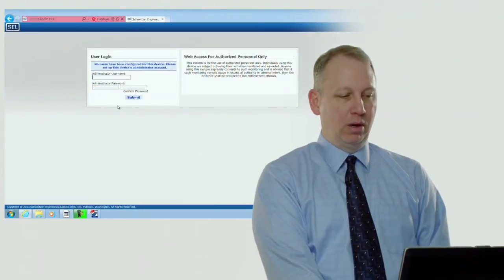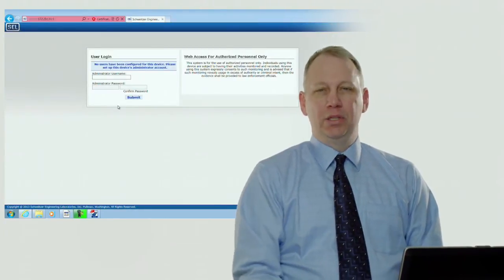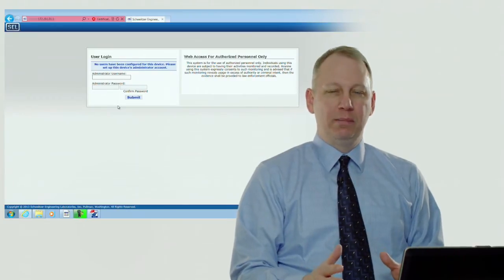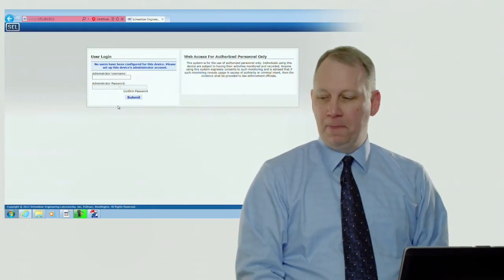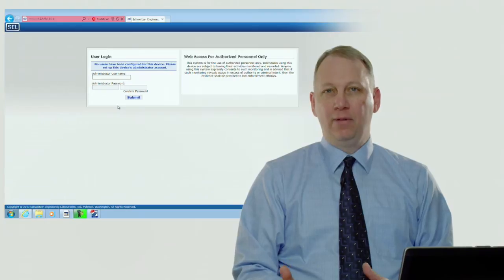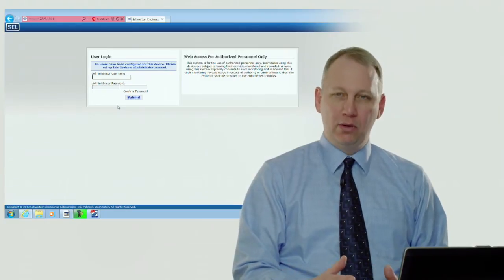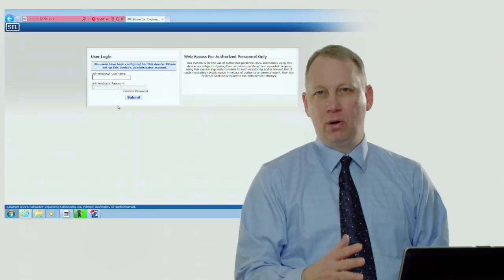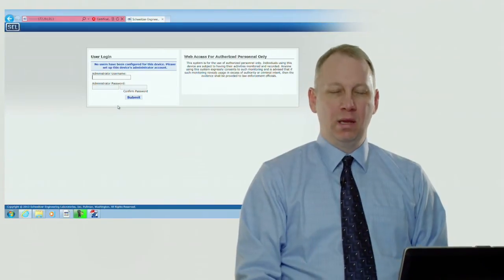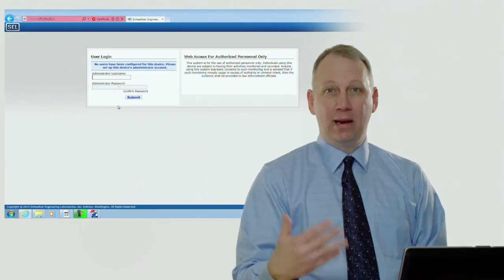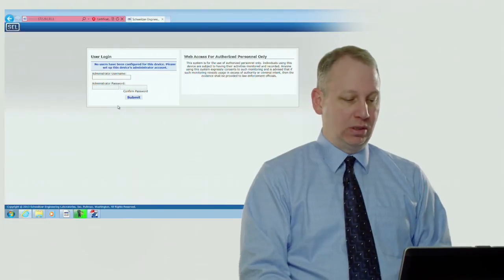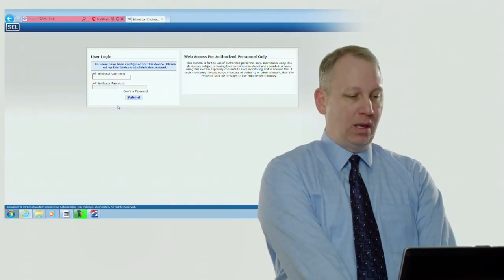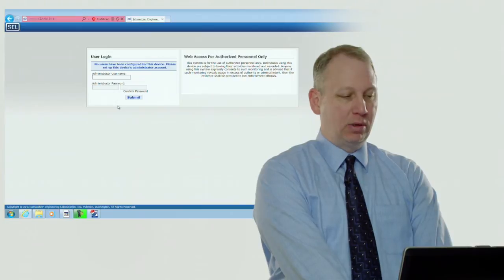Your IT group could make a signed certificate and load it in, but for now we're just going to say continue on with the website. We're going to go to the next screen which allows you to set up the initial admin username and password. The RTAC doesn't have a default username and password and it doesn't have a backdoor username and password. NERC CIP requirements require you to have something that's totally clean and something that somebody can't hack into later. So we're going to set up the initial username and password.